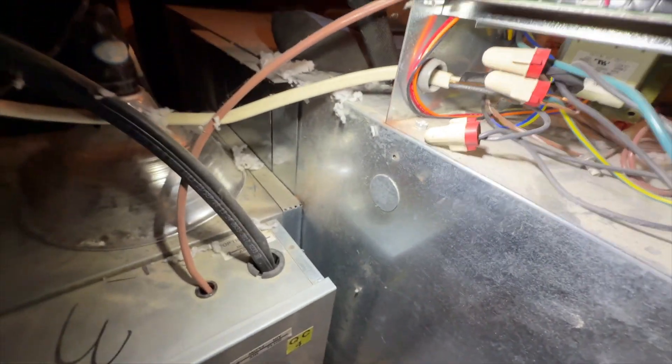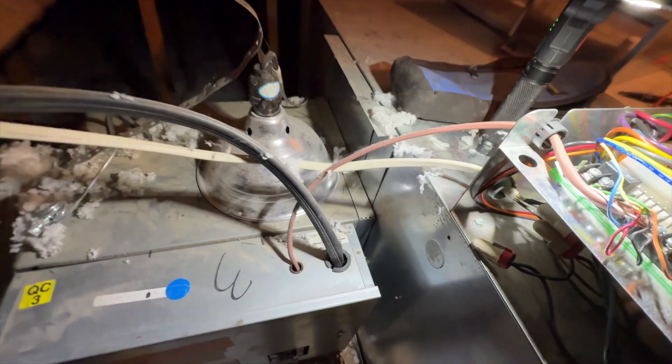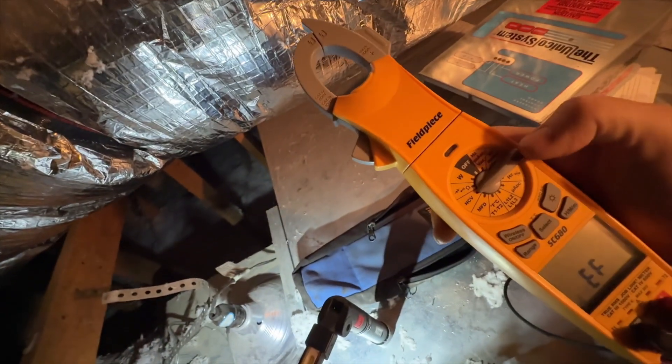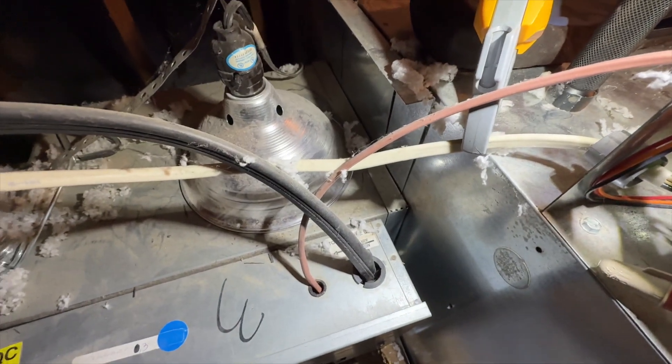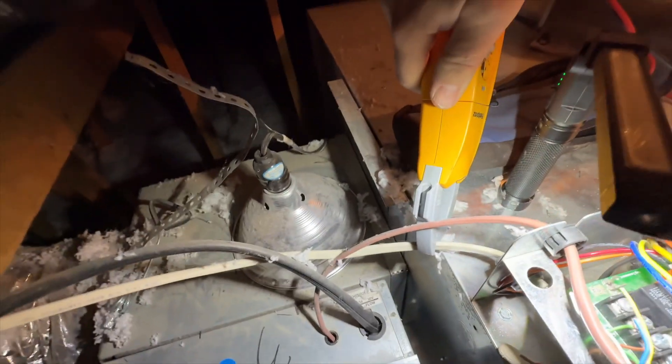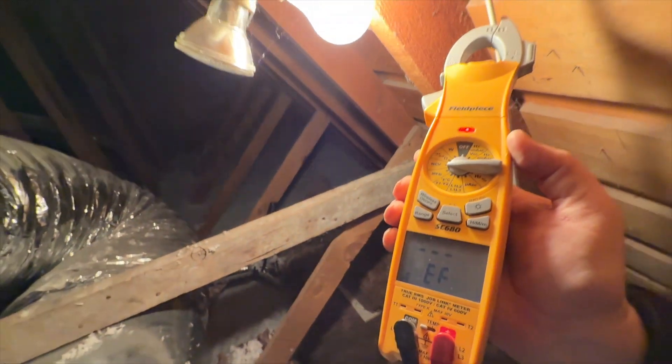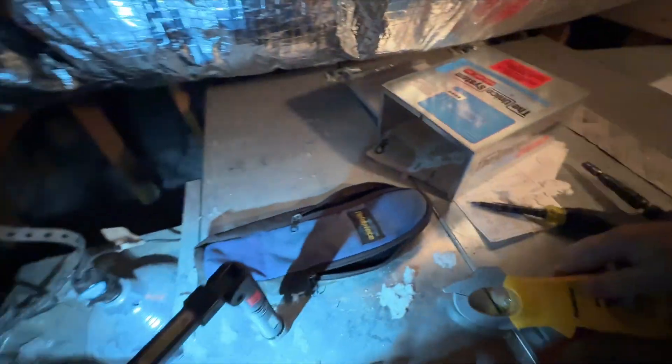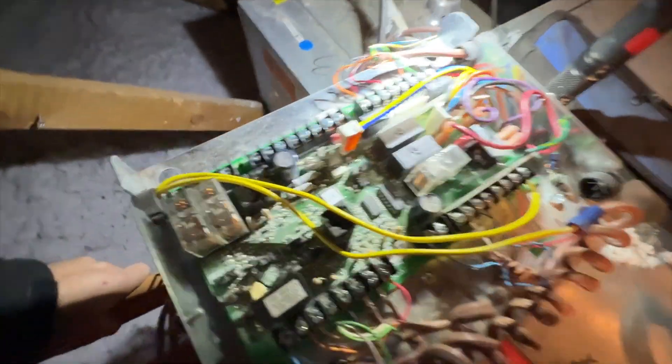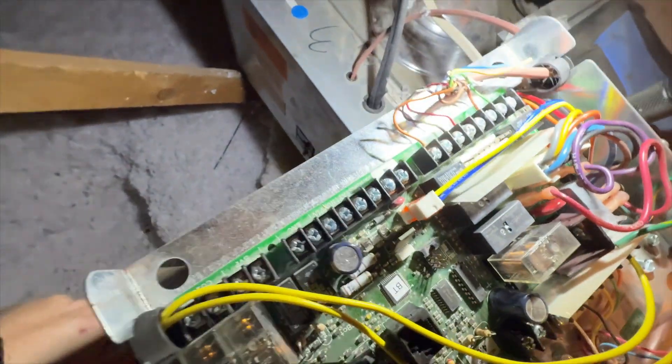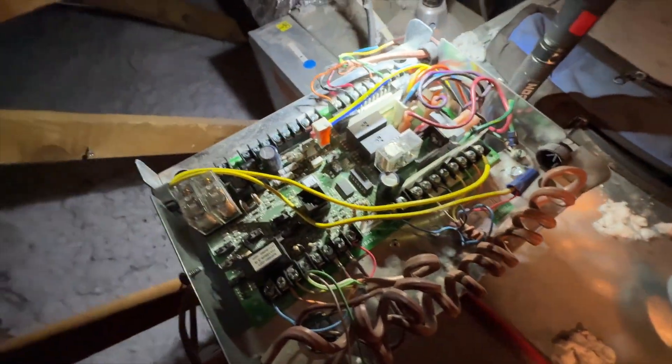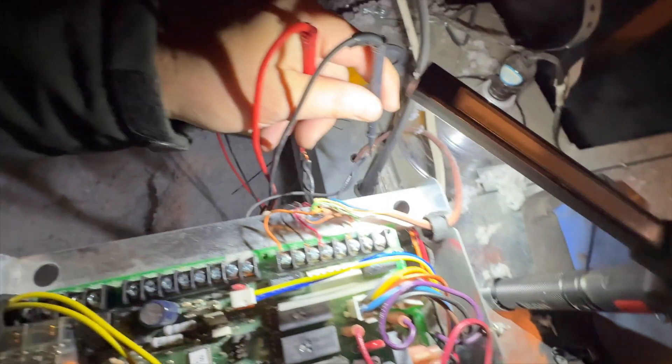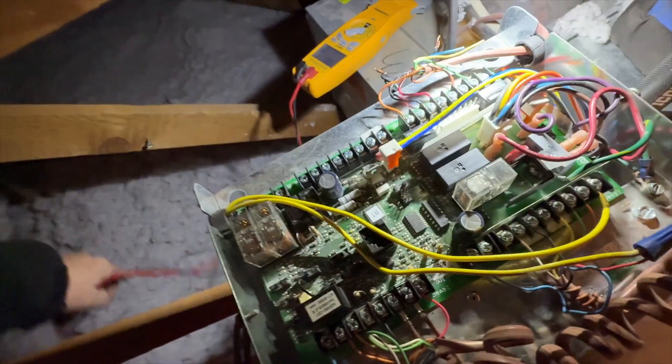A quick way is we can set our meter to NCV, which is non-contact voltage. So I do have high voltage, it appears. Just to show you here, see. So we may have a bad transformer. We need to find out where that transformer connects and then check from there. All right, so I'm checking the wires just to be sure and we have, you can't see it, but there's 240. So I have high voltage.